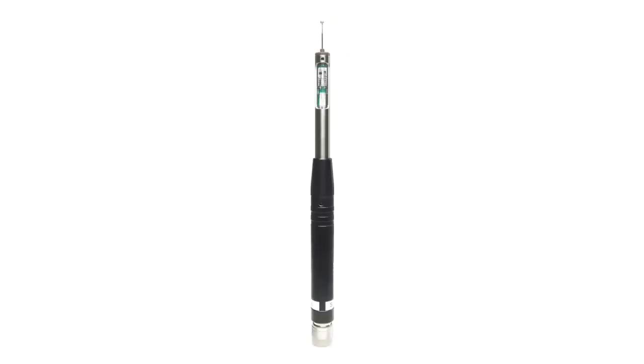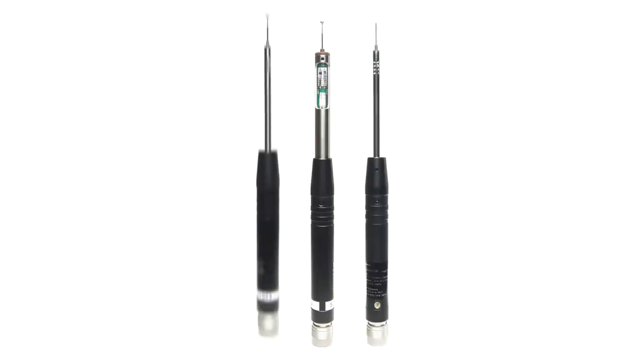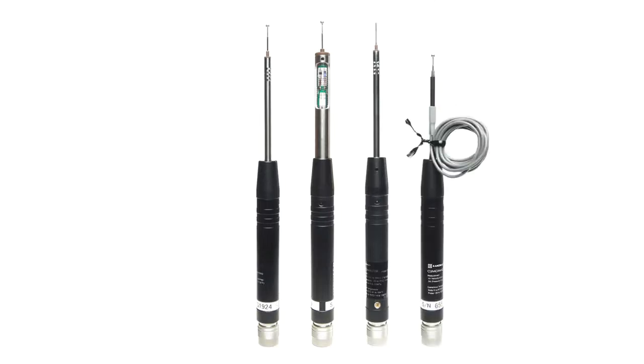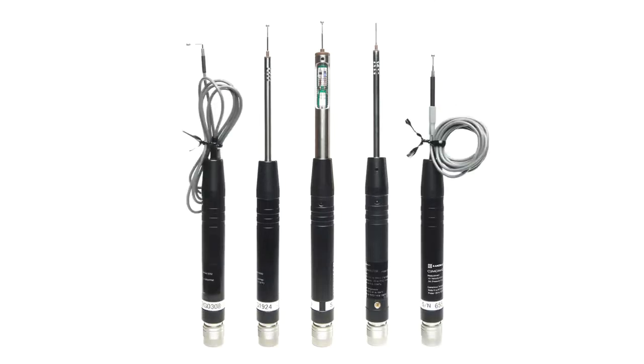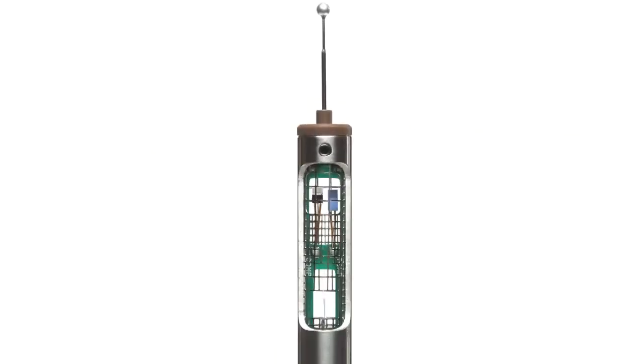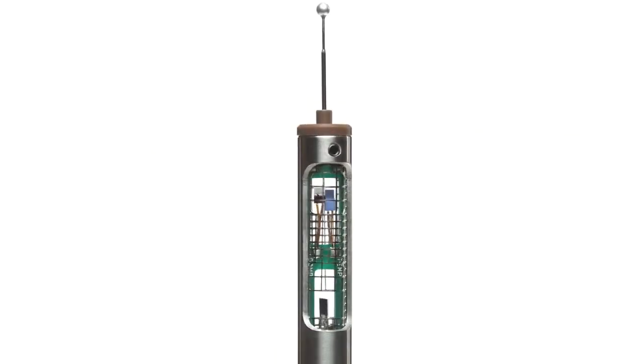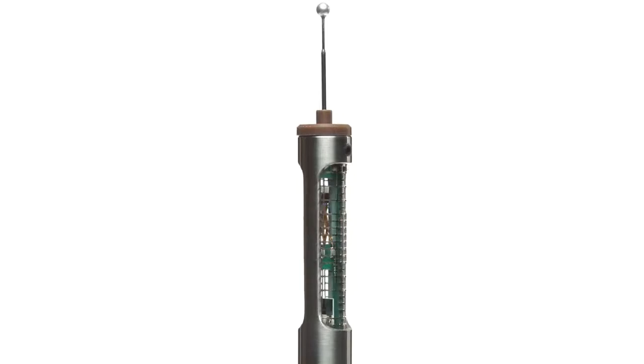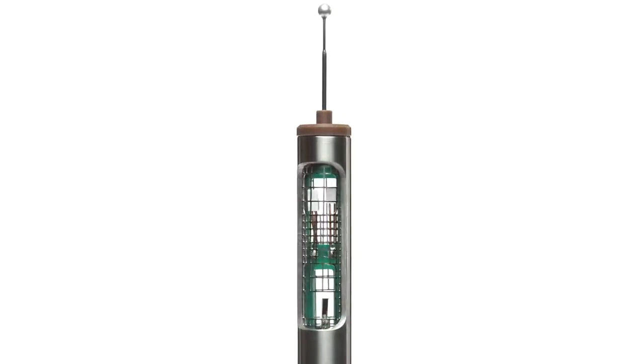In turbulent airflow conditions, where the air is moving in many directions, you will want an omnidirectional probe like Model 6533, 6542, 6543, 6551, and 6552. Each of these probes has a horizontal 360-degree dynamic characteristic that measures air velocity all around it. Because the probe utilizes both an air velocity sensor and a temperature compensation sensor to accurately measure air velocity, it's necessary that both sensors are evenly exposed to the airflow under the same temperature conditions.